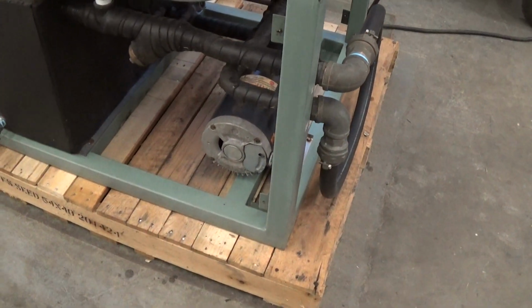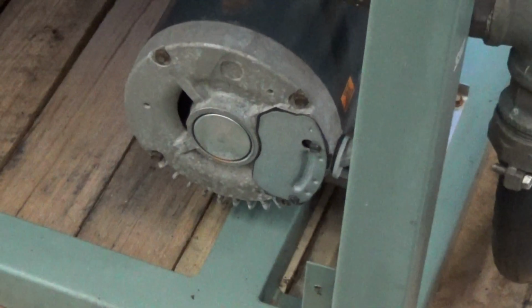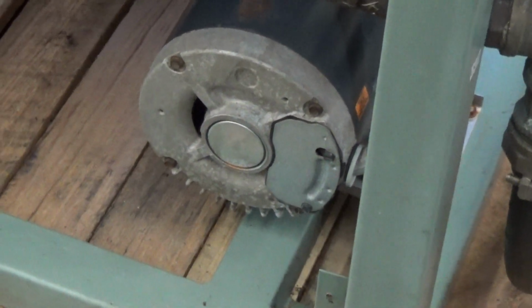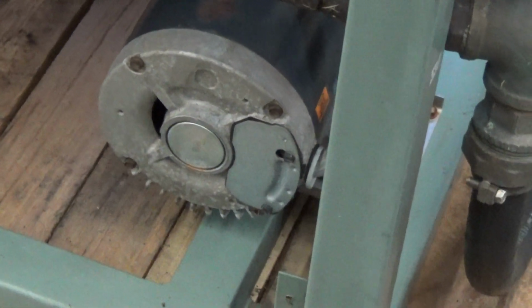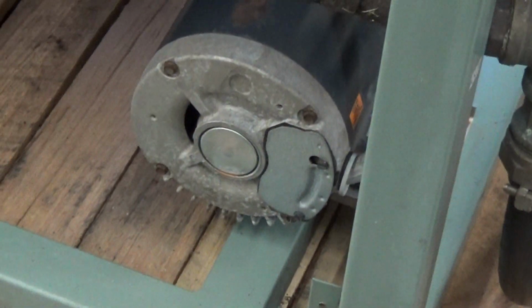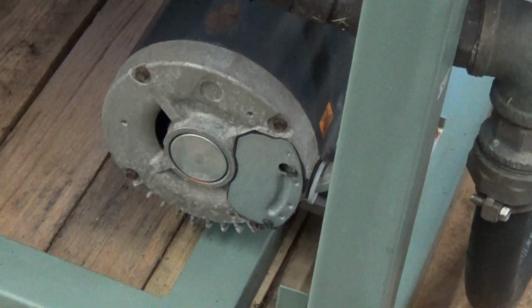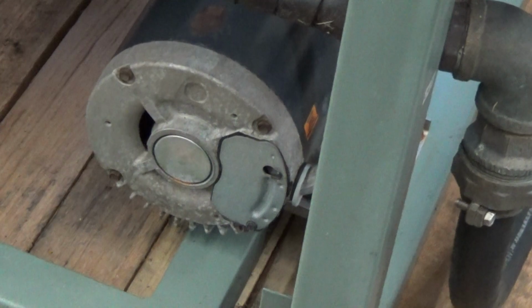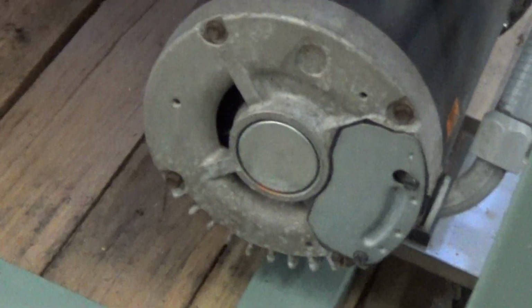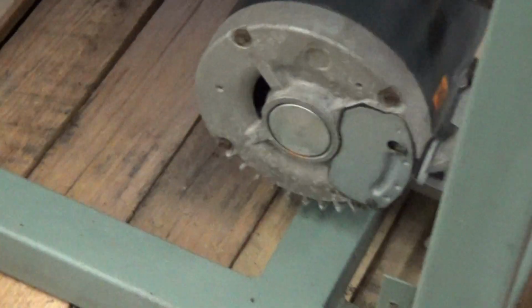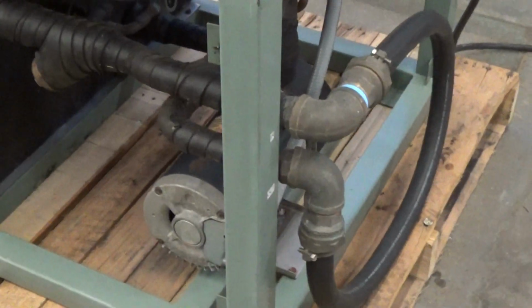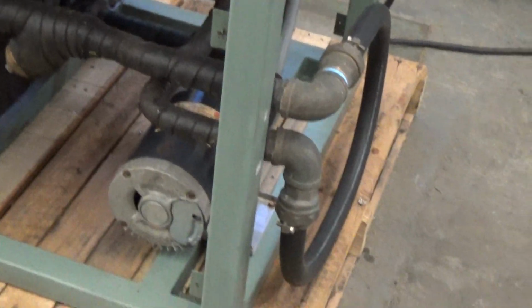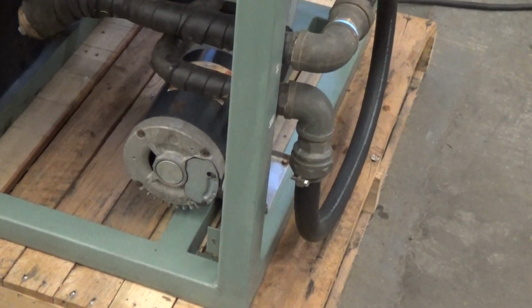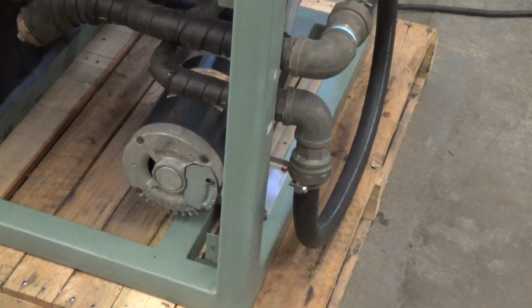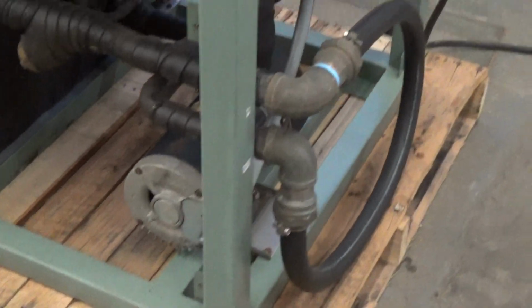When you do first get the unit, you saw me just turn the pump on there. To check phase rotation, it's good to have a second set of eyes or hands, and you just bump that pump switch, and with a flashlight here we want to make sure that that pump is rotating clockwise while looking from behind right through that little vent window. If it isn't, and of course you should have a licensed electrician, then you should change any 2 of the 3 incoming power legs.